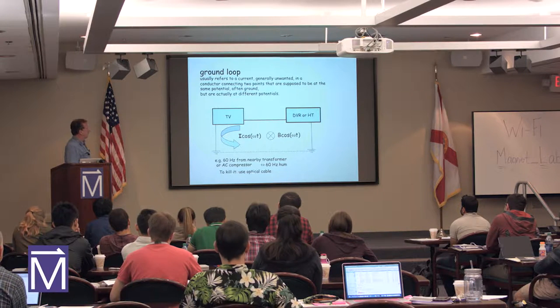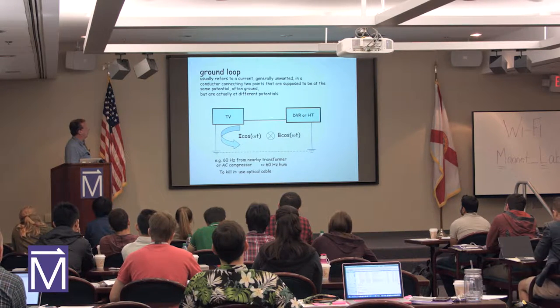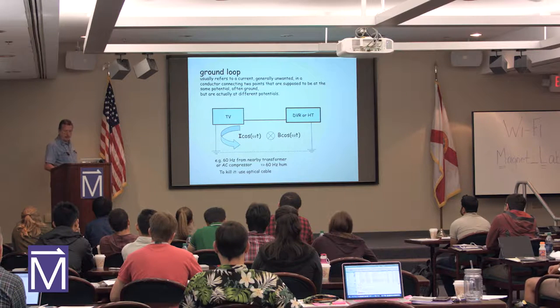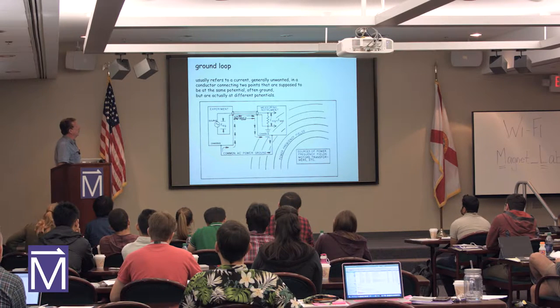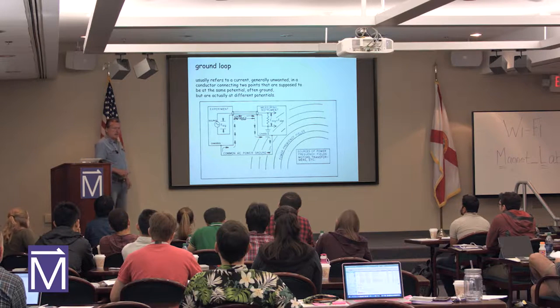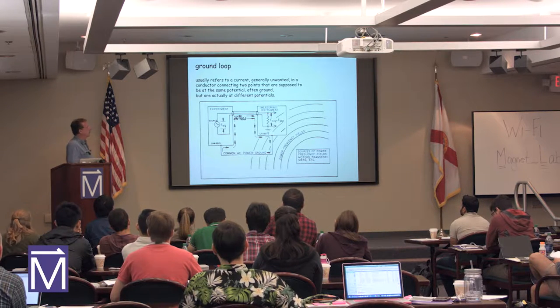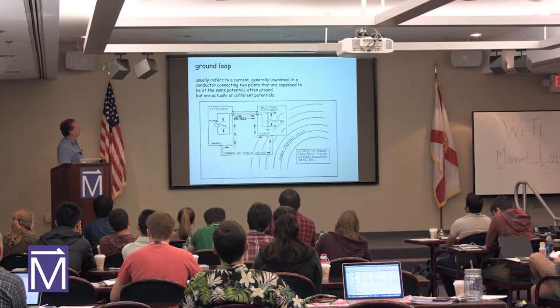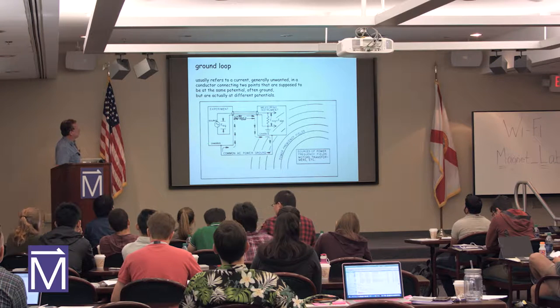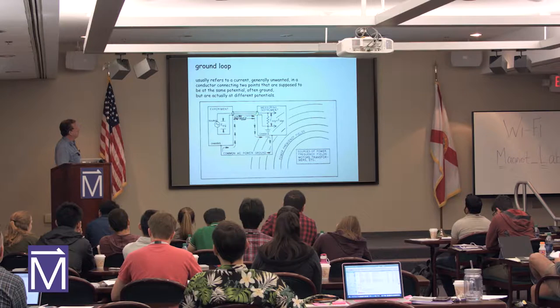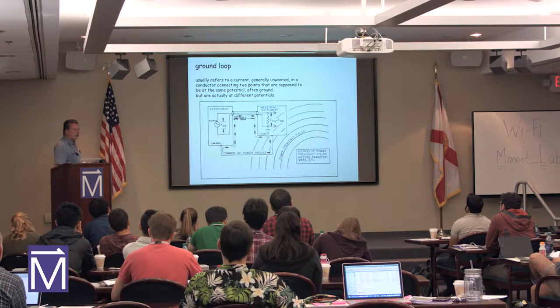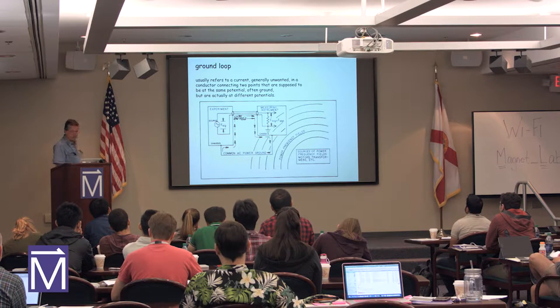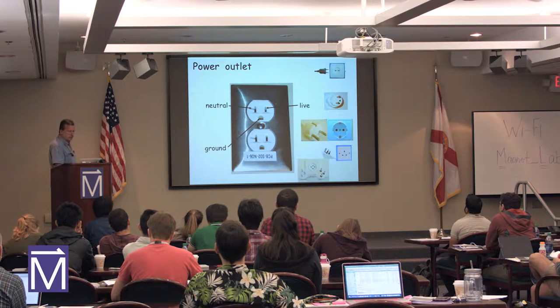To kill it, the best thing is to use optical cable between those things. Also, we use optical insulation in our lab to isolate computers, which are very noisy, from measuring setups. This is the same, but here you can see the experiment, measuring instrument, and ground loop, which results in some additional voltage on the input, which results in noise.